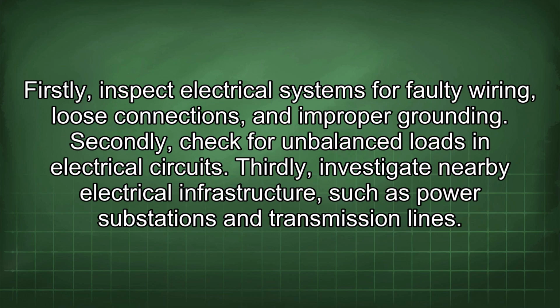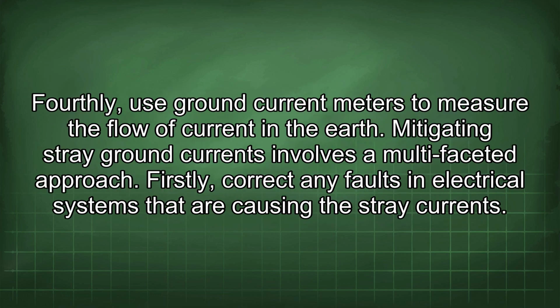Firstly, inspect electrical systems for faulty wiring, loose connections, and improper grounding. Secondly, check for unbalanced loads in electrical circuits. Thirdly, investigate nearby electrical infrastructure, such as power substations and transmission lines. Fourthly, use ground current meters to measure the flow of current in the earth. Mitigating stray ground currents involves a multifaceted approach. Firstly, correct any faults in electrical systems that are causing the stray currents.